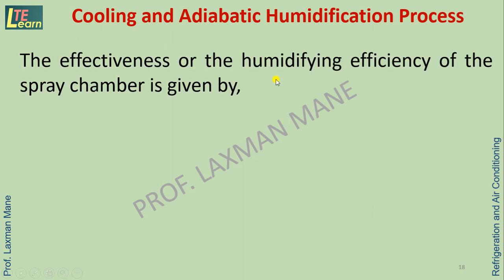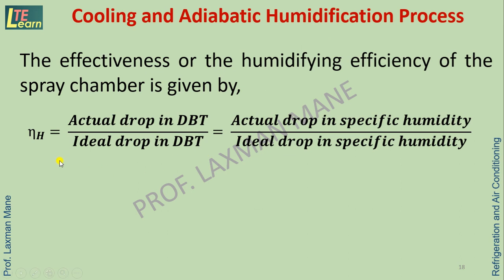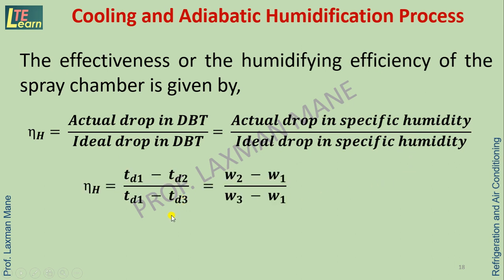The effectiveness or humidifying efficiency of the spray chamber or air washer is given by the formula: humidifier efficiency equals the ratio of actual drop in dry bulb temperature to ideal drop in dry bulb temperature, or equivalently the ratio of actual drop in specific humidity to ideal drop in specific humidity — that is, (W2 − W1) / (W3 − W1), where W1 and W2 are specific humidity at inlet and outlet of air, and W3 is the ideal outlet specific humidity.